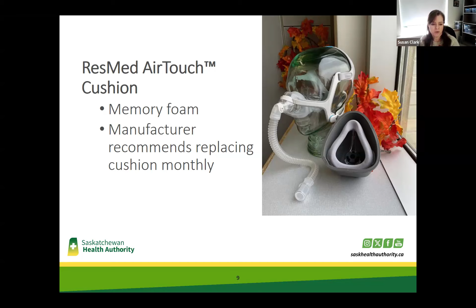So here are the actual recommendations for the AirTouch cushion. If you see any deterioration, discard it and replace it. Clean with alcohol-free wipes only. Make sure you keep it dry and away from liquids. Don't expose it to direct sunlight. Don't use any domestic cleaner or domestic cleaning devices on it. Don't use alcohol wipes, and don't submerge it in liquids, as I mentioned.